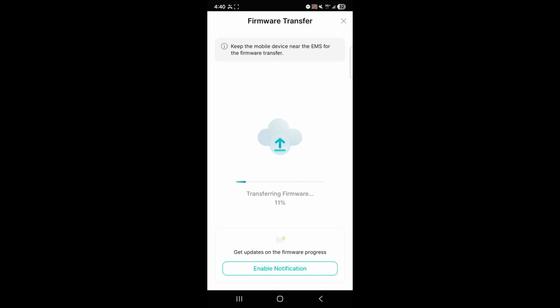Your commissioning device will download the firmware update over cellular data, so a cellular data connection is required. This update can be pre-downloaded from the app home screen before starting the commissioning process. When the update is complete, click Next. This firmware update cannot be skipped. If the firmware cannot be updated through the app, the installer can push the firmware update automatically with a USB flash drive. If you have any issues with this process or have any questions, please call our support line at 888-249-7750.